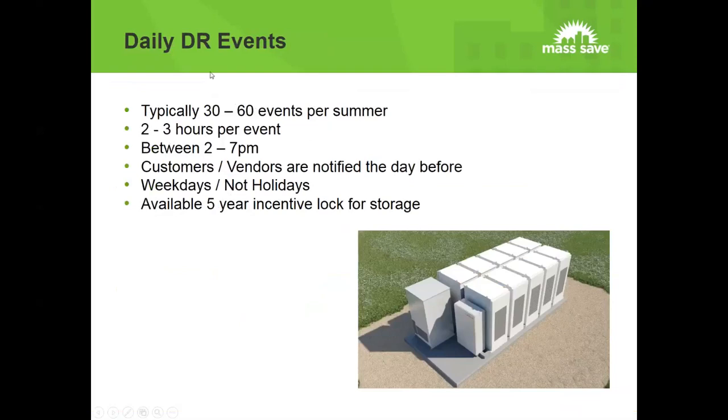So this is our battery program, or our daily dispatch program. Like I said, we'll call 30 to 60 times per summer. The events last from 2 to 3 hours. They're somewhere between 2 and 7. Now I know that math doesn't quite add up. There's more hours than 2 or 3 between that. That's because there's a moving window there. Sometimes we'll call from 2 to 5, other times from 3 to 6. But customers will know that a day ahead. Never on weekends, never on holidays.